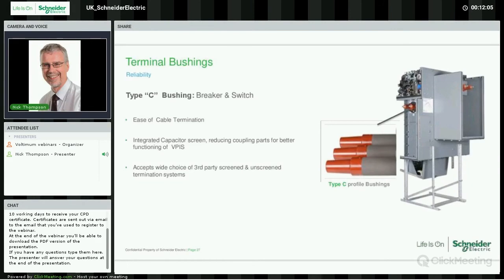will be connected on the ring, as we can see there with the bushings highlighted. This is where your main cables are bolted on, and traditionally there's been a bushing profile which doesn't meet the latest IEC bushing profile there. We have what's called a Type C. There are others to choose from, but Type C seems to be the most common one, which is used on 11 kV distribution switchgear. The grey bit that you can see there is a metallic earth screen, which is all part of the tank.